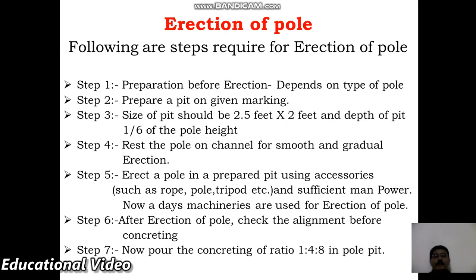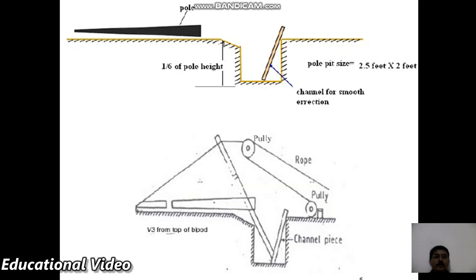The method of erection of a pole follows these steps: first, prepare the pit based on the type of pole. The pit size should be 2.5 by 2 feet, with depth equal to one-sixth of the pole height — for a 6-meter pole, that is 1 meter depth. Then erect the pole using accessories and sufficient manpower or machinery. Check alignment before pouring concrete in a ratio of 1:4:8 in the pole pit.